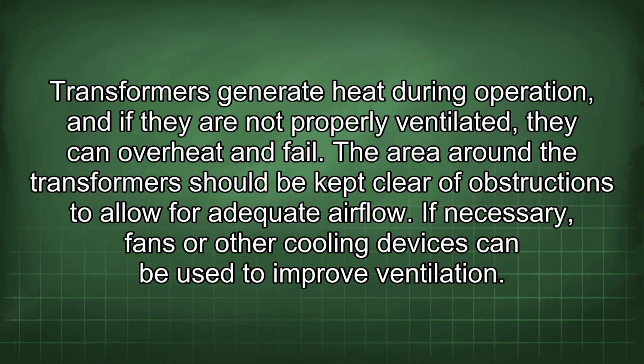Transformers generate heat during operation, and if they are not properly ventilated, they can overheat and fail. The area around the transformers should be kept clear of obstructions to allow for adequate airflow. If necessary, fans or other cooling devices can be used to improve ventilation.